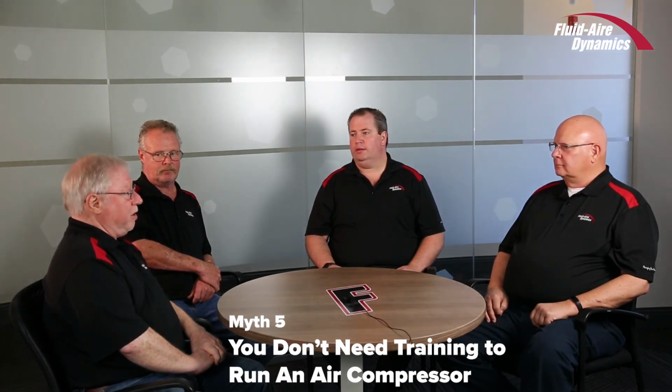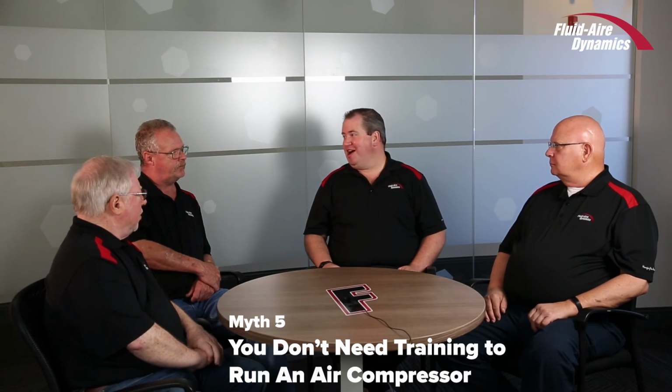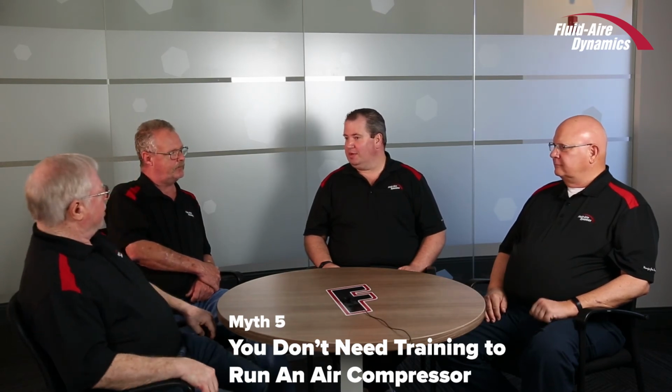You'll hear them, okay? And the ones you can hear need to be fixed. Like I said, you can get a lot finer than that and get down to all the little leaks, but the big ones are the ones that cost you the money. Yeah, if you consider a good quality coupler set is about $13, $15 for a good 8-ball coupler set, and 1 CFM is costing you $35 in a single shift. It's pretty fast ROI, isn't it? Have your maintenance department get that repaired.